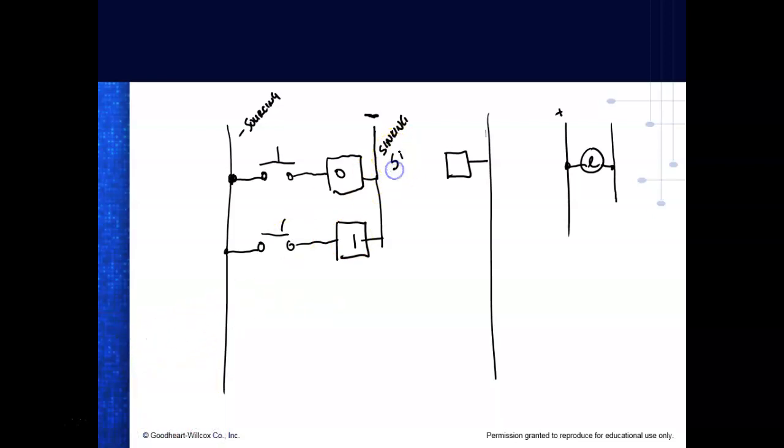And this came up through digital, guys. This is DC. AC has no polarity. So if I had AC inputs, we would just have a common. What happens is, if I keep hooking up input devices, then over here on my PLC I'm going to use a negative common.